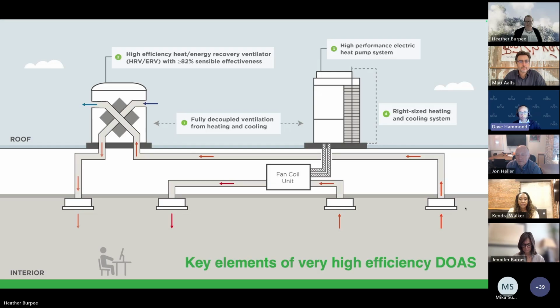So just to call it out at a high level, the key elements of very high efficiency DOAS include, first and foremost, fully decoupled ventilation from the heating and cooling system. You can see on this diagram on the left, you have your ERV or HRV, and on the right, this one tends to lean more towards a VRF, or variable refrigerant flow system, working in separate distribution.